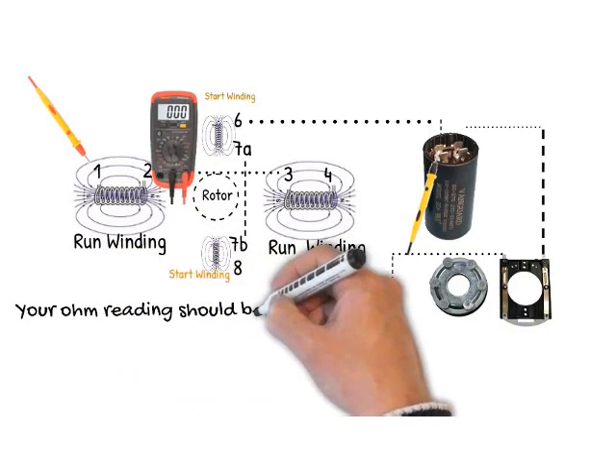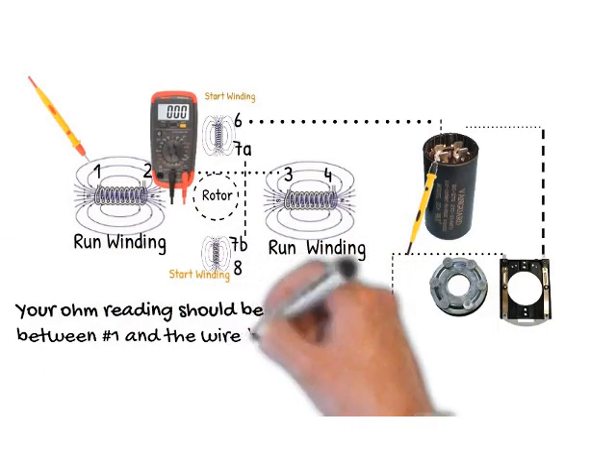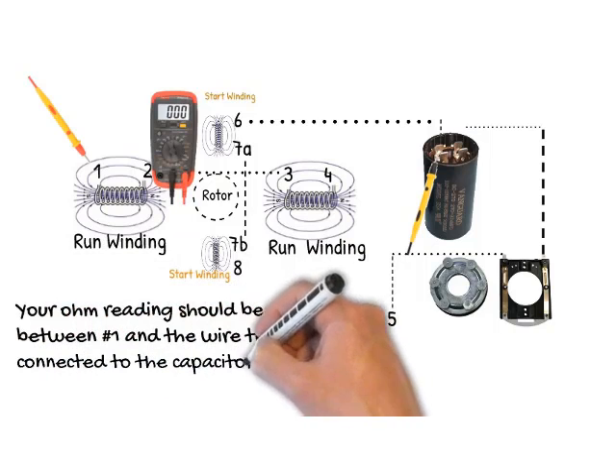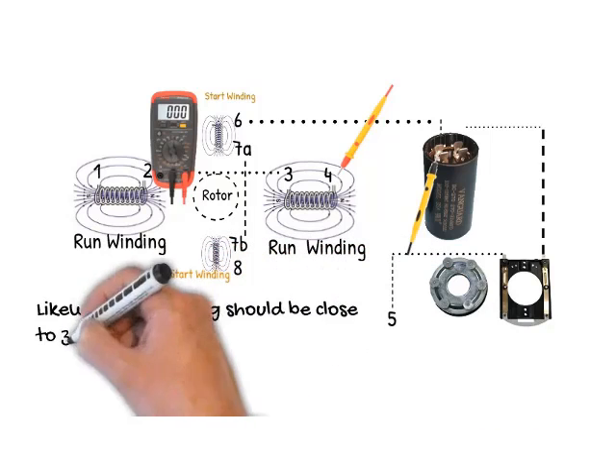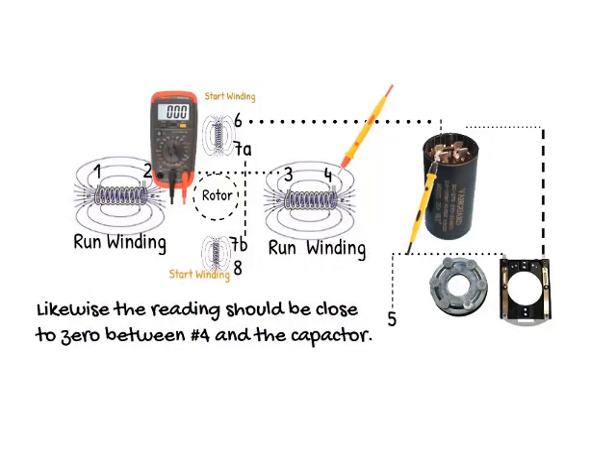Your ohm reading should be close to zero between number one and the wire that remains connected to the capacitor. Likewise, the reading should be close to zero between number four and the capacitor.